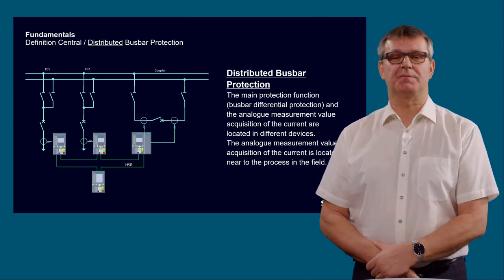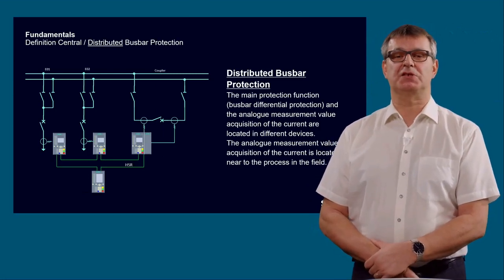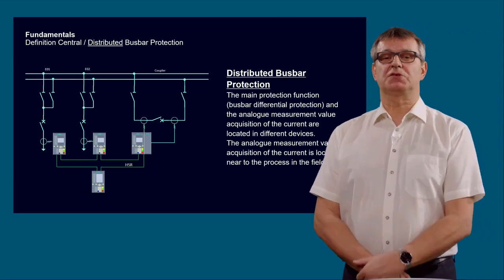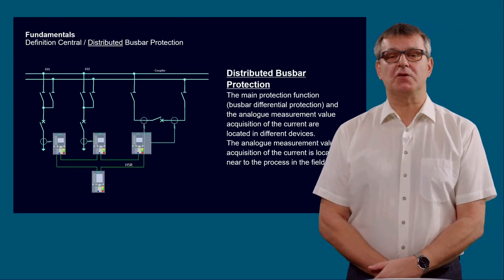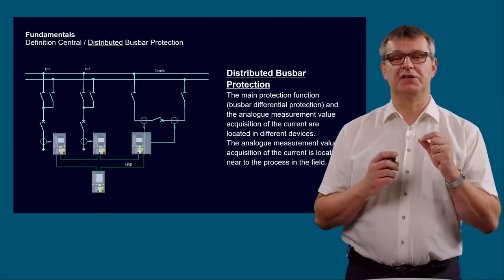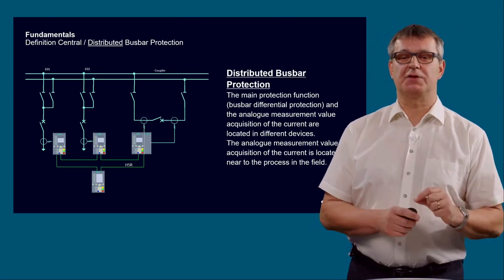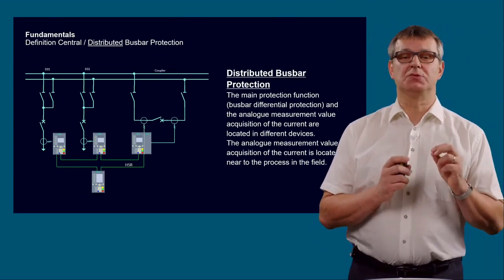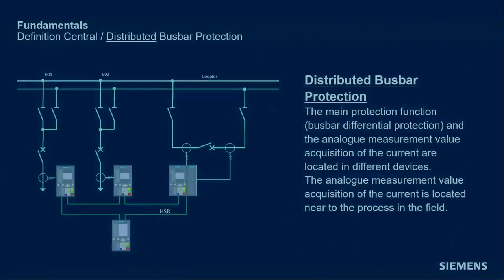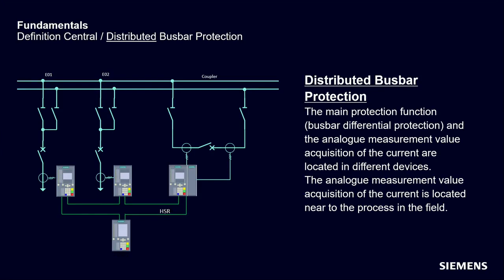The distributed busbar protection. What is it? The main protection function, the busbar differential protection, and the analog measurement value acquisition of the current are located in different devices, and these devices are typically located near the process. So here in this shot, in a distributed busbar protection, the central unit will be this middle one at the bottom, and the bay units or merging units are located directly at the process, connected to the primary current transformer. In this case, we are speaking about a distributed busbar protection.